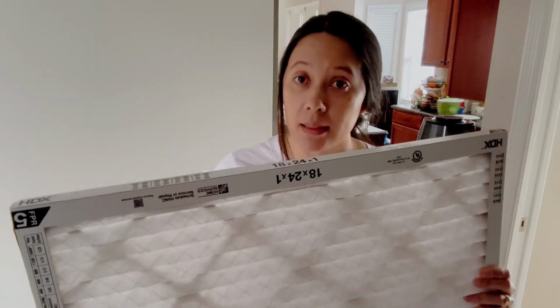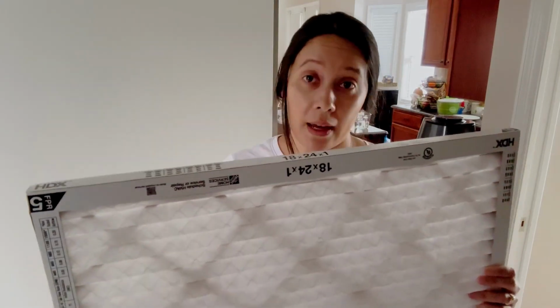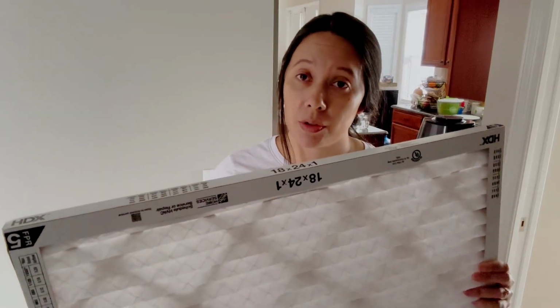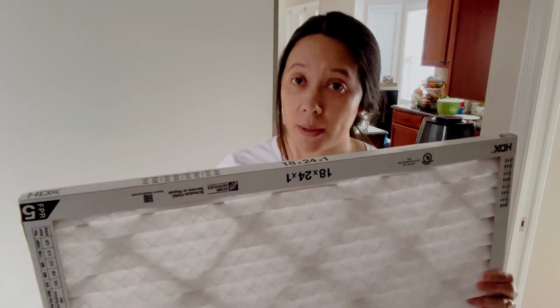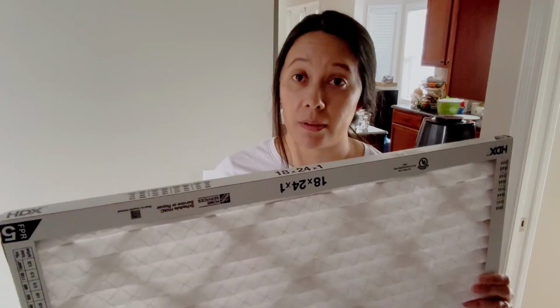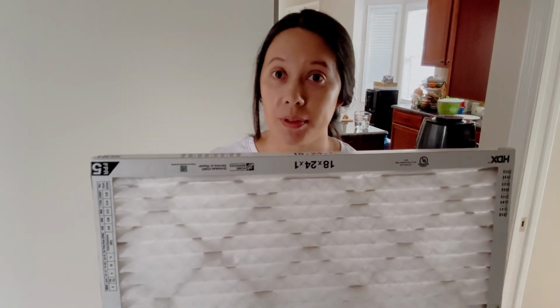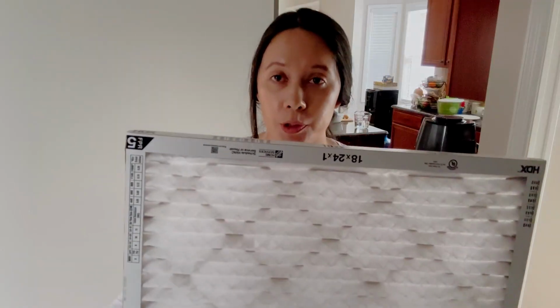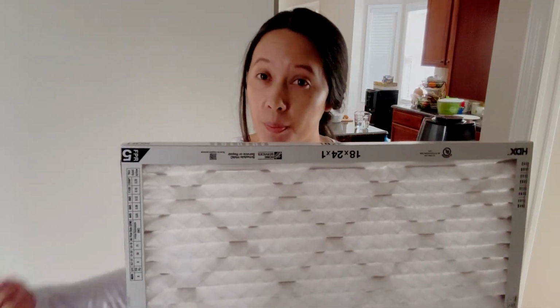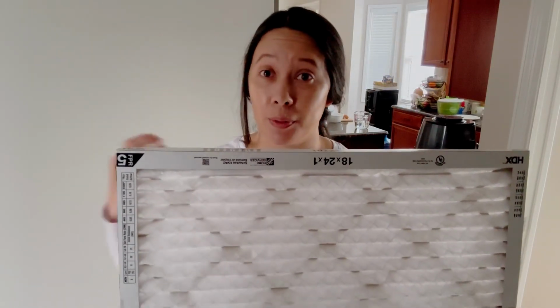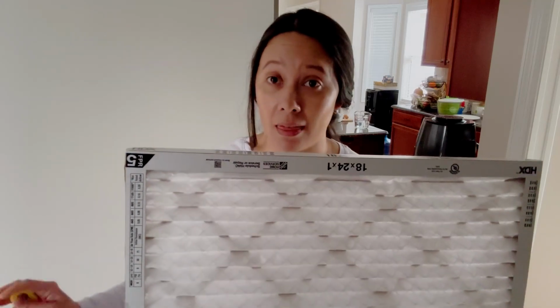The rating on this is a MERV 8 or an FPR 5, and most HVAC professionals are going to recommend that for residents, you don't go above MERV 11. Something like a MERV 13 is designed for use in hospitals, schools, or commercial buildings that have a more robust system, where your residential HVAC is going to be nothing like that.